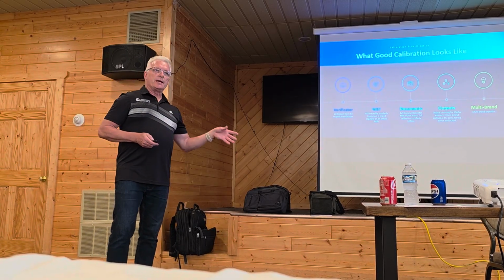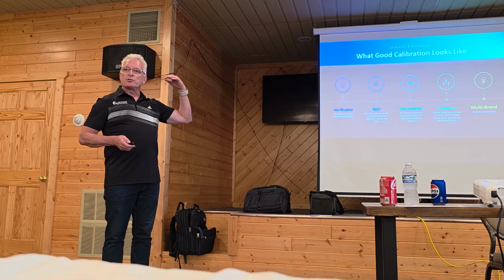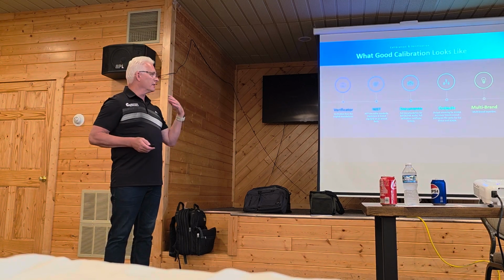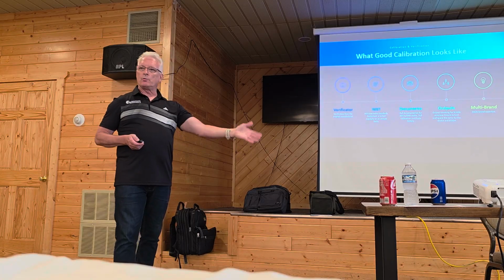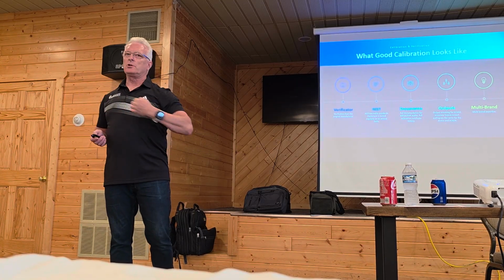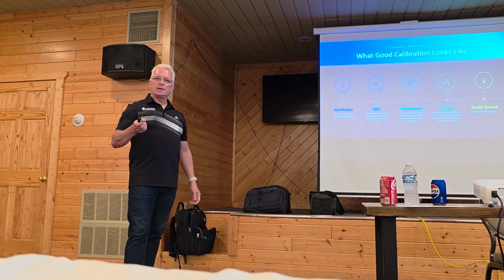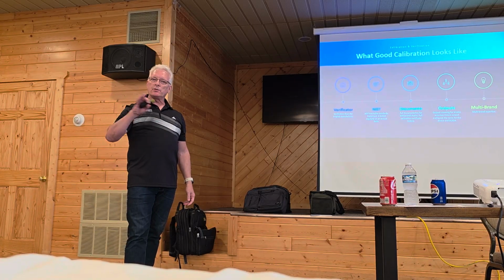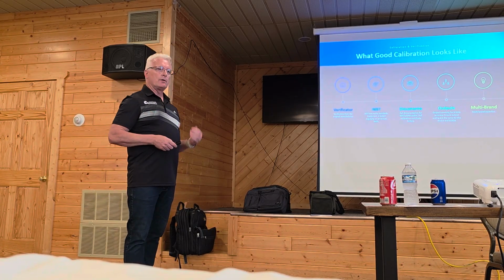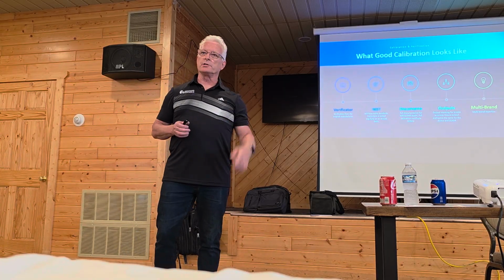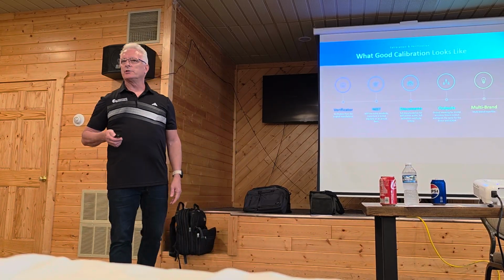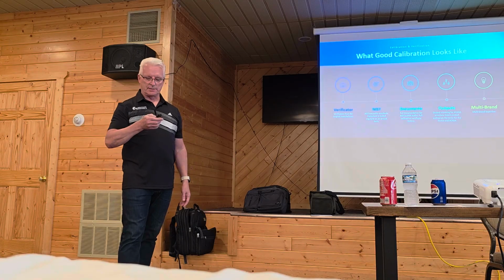So having a verificator, making sure they're tested by an outside source, which is NIST, making sure it's accurate and right, and then documenting what it was, as found and as left, checking the inputs and outputs and all the setup to make sure it's right, and then also being able to do multiple brands with one person. That's important, otherwise you're calling out two or three people to do things.